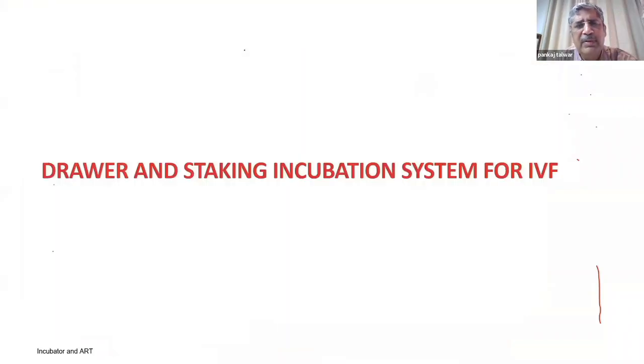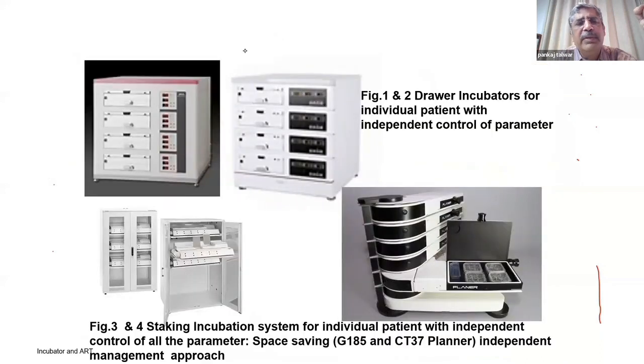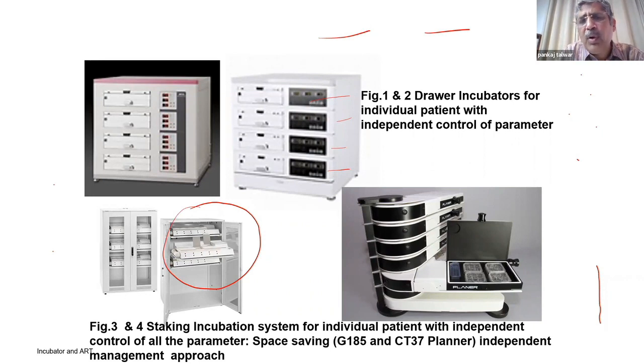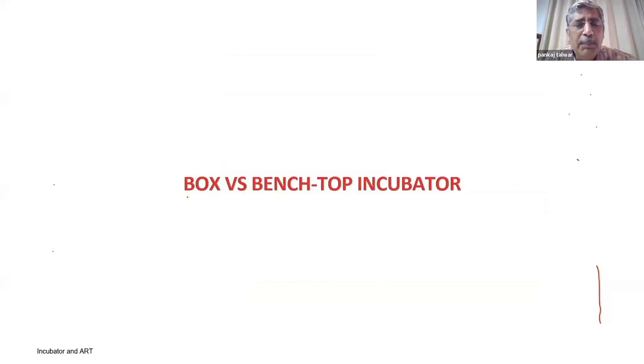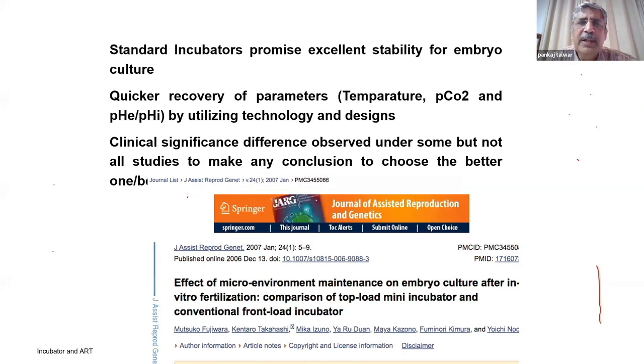So this is the closer view of a dry gas incubator. Nowadays incubators occupy a lot of space, so we stack them one upon another. They're called stacking and drawer incubators. This incubator will take nearly 1 meter of space. They're so big that in the lab they will take around 1 meter by 1 meter by 1 meter. Labs are small, so we stack them. We have almirahs like this where we can stack 3 to 4 incubators, going vertically. Box versus benchtop incubator: I've told you that benchtop is any day better, and non-humidified benchtop is better. So nowadays they're going to flatbed benchtop incubators.